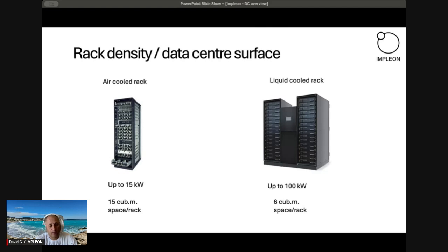The main driver is new AI-dedicated software and new servers covering those demands. If we look at the new generation of servers, the density of the racks can be 100 kilowatt in comparison with the conventional 15 kilowatt. But at the same time, the space requested for those racks is much less, because with liquid heat transfer we don't need a raised floor, a ceiling, or a cold aisle and hot aisle. That reduces the space from the infrastructure point of view and increases density 7 times from the server point of view. So overall, 7 by 3 is 21 times denser. So we need 21 times less space, and less embedded carbon of the building.